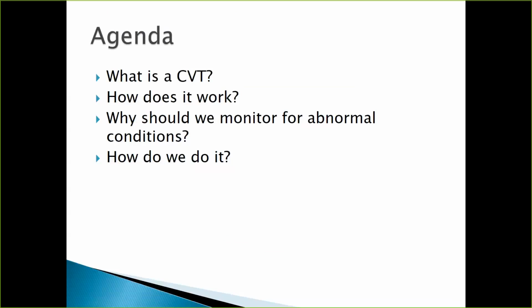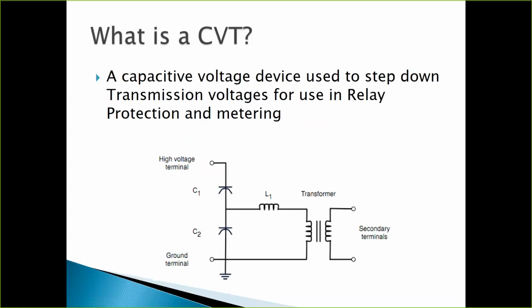So with that, what is a CVT? The textbook device definition is it's a capacitive voltage device used to step down transmission class voltages for use in relay protection and metering. What you have here is a simple one-line diagram. This is the terminal where you'd have your line voltage hooked up, be it 100 kV, 230 kV, even 525 kV in the case of Duke Energy. And basically, it is a voltage divider.